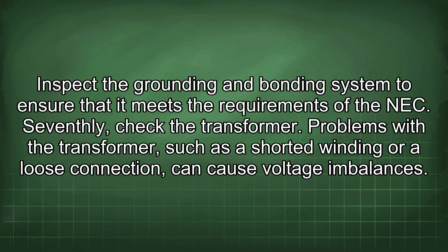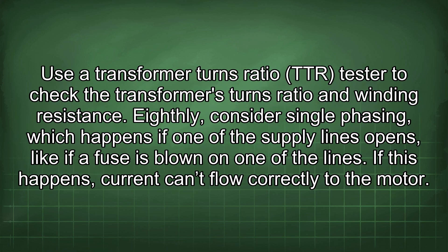Seventh, check the transformer. Problems with the transformer, such as a shorted winding or a loose connection, can cause voltage imbalances. Use a transformer turns ratio TTR tester to check the transformer's turns ratio and winding resistance.